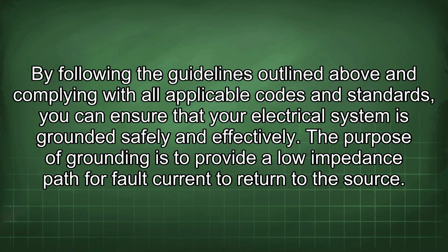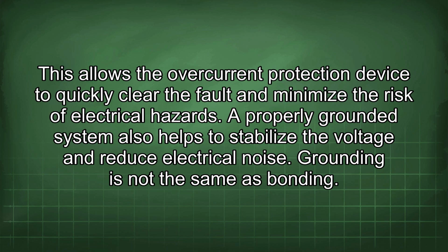The purpose of grounding is to provide a low impedance path for fault current to return to the source. This allows the overcurrent protection device to quickly clear the fault and minimize the risk of electrical hazards. A properly grounded system also helps to stabilize the voltage and reduce electrical noise.